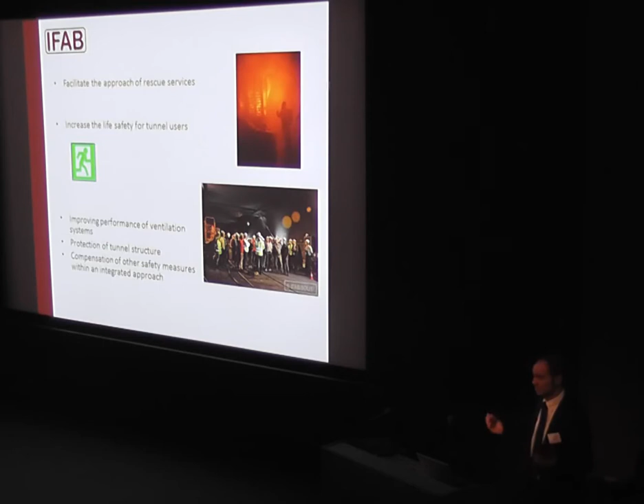The effect of water mist in tunnel fires: you already learned a little about water mist, so I won't go into detail. We have small droplets. Of course, the design of a water mist system is completely different for a building than for inside tunnels. For example, for electronic switchgear cabinets or even office areas, you use water mist systems usually with a droplet size much below 100 microns. For tunnels, no way, no chance at all — you need big droplets because you have to get the droplets into the fire.